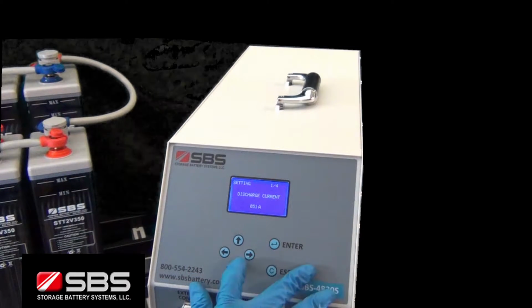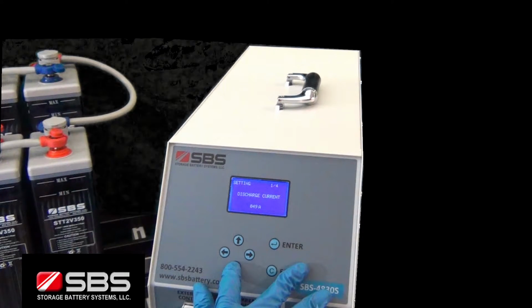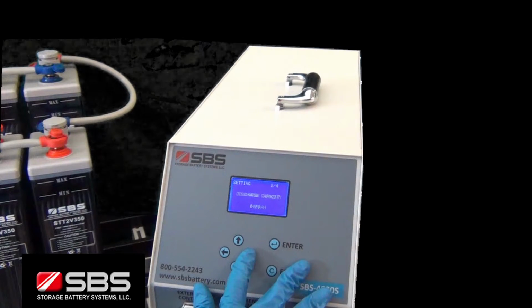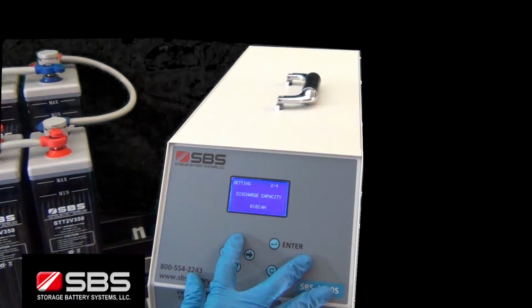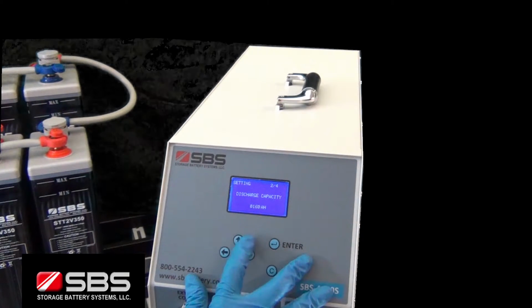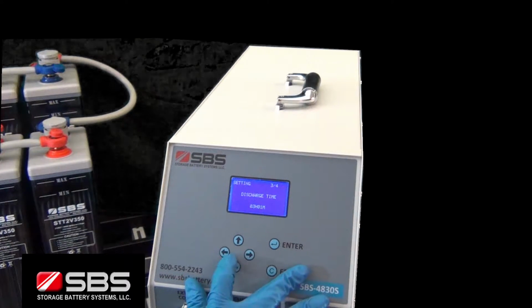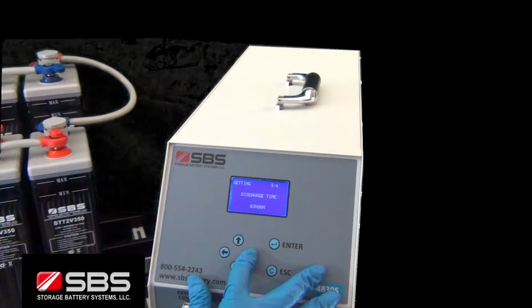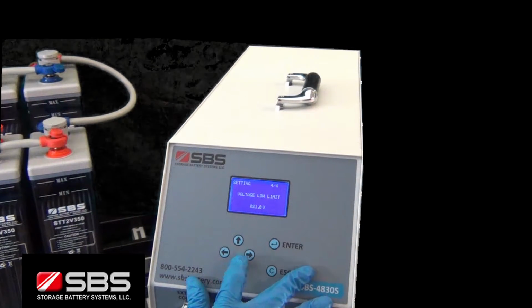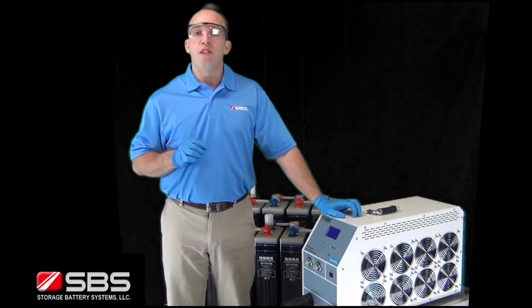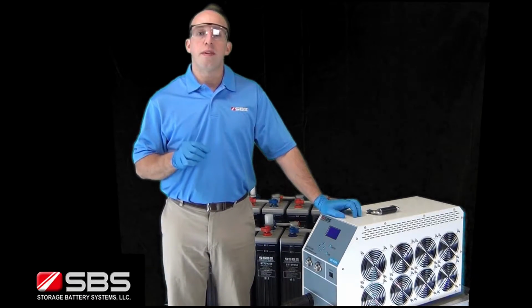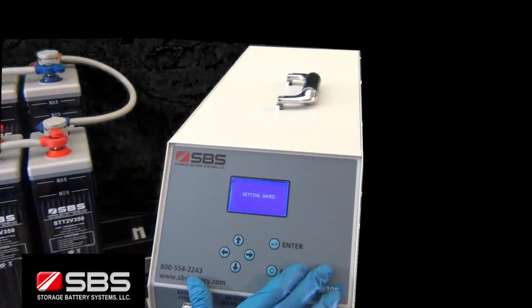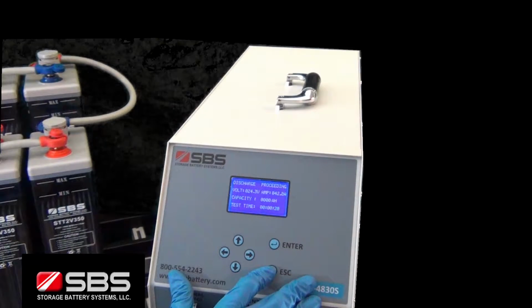Set the discharge current by using the up and down arrows. Once this is set, press the right arrow to go to the next parameter. Next, set the capacity in amp hours needed to be discharged, again by using the up and down arrows. Press the right arrow to go to the next parameter. If the capacity discharged reaches the setting value, the SBS S-Series will terminate the test automatically. Finally, set the low voltage stop threshold with the up and down arrows, and press the right arrow to continue. If the voltage reaches the value entered, the SBS S-Series will terminate the test automatically. Now, press enter to confirm the settings, and the LCD screen will show a settings saved message. Press escape to go back to the main menu.